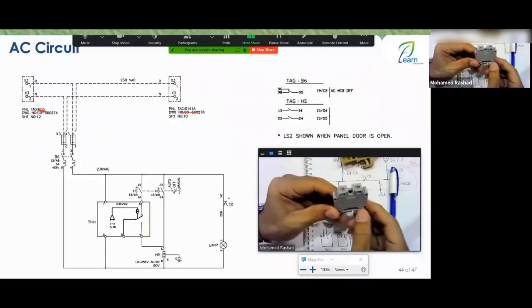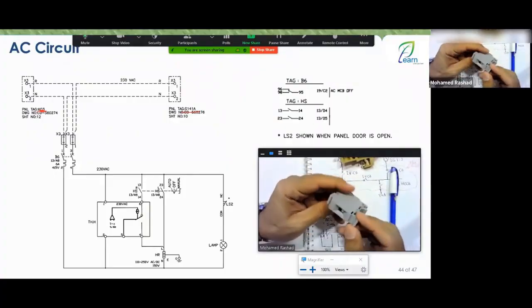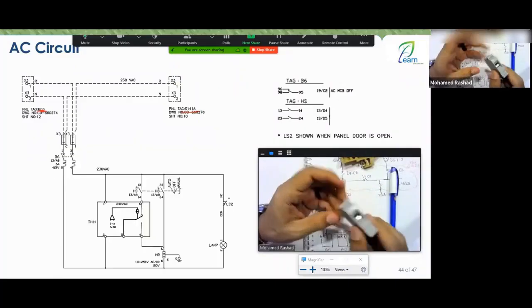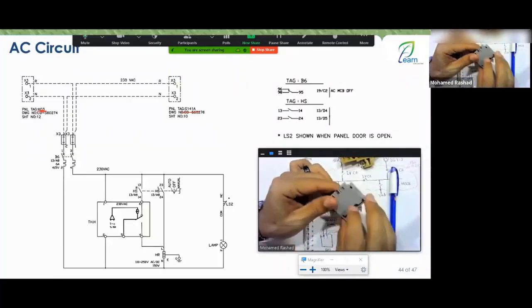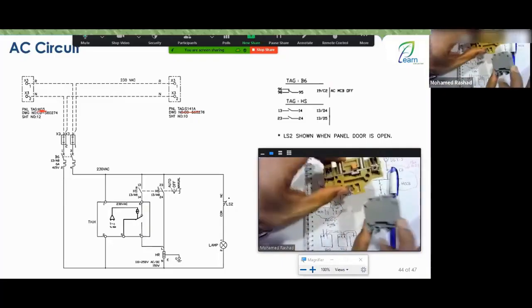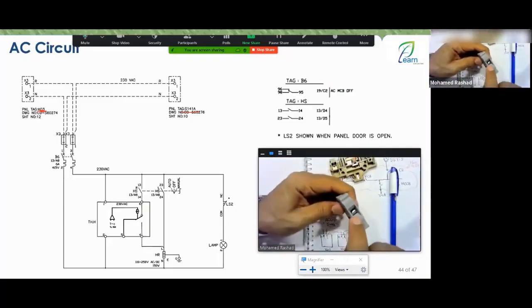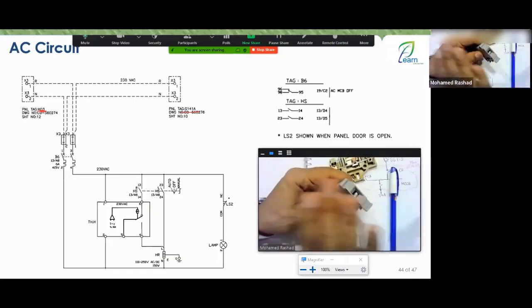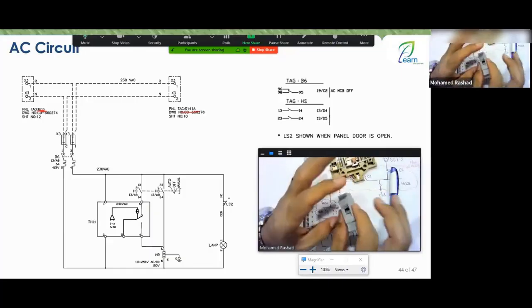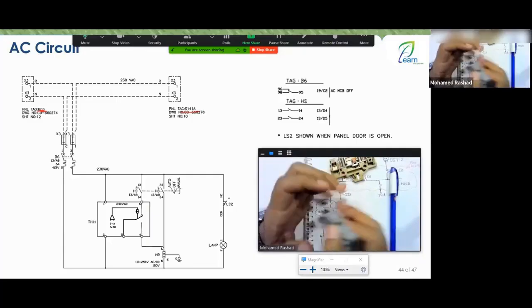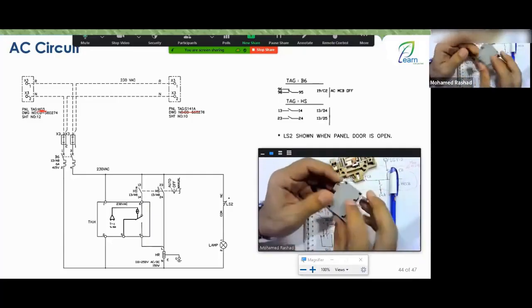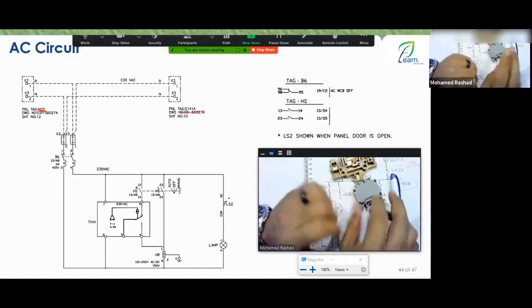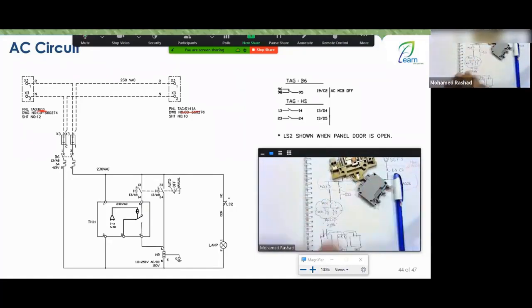This is what we call the fixed type. What is the fixed type? The standard around the whole world is that each terminal in a terminal block, any type of terminal block, cannot accommodate more than 2 wires. It's impossible. This has nothing to do with Skeko, Ranko, or whether it's in Egypt or outside of Egypt. It has no relation. Any terminal in a terminal block, for any type of terminal block, cannot accommodate more than how many? More than 2 wires.